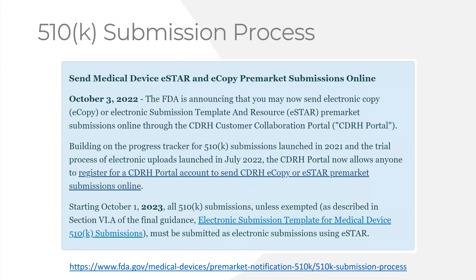The 510K process has been updated. Anyone familiar with 510Ks in the past knows it had 20 sections — sections 1 through 20. Some people added a 21st section for the RTA checklist. You were required to provide a table of contents linking to each section — for example, section 10 should always be your device description, section 11 your executive summary, section 12 your substantial equivalence. They've done away with the need for a table of contents because with the new eStar template, you can only organize it one way. Everything is always in the same order.